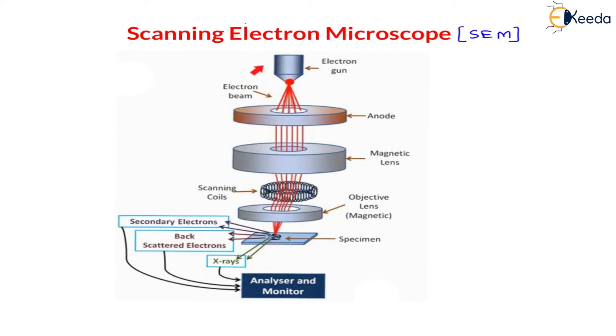Here you can see the actual diagram and setup of this scanning electron microscope. You will see the electron gun — a gun through which the electron beam comes out. There is also an anode. On this anode we provide a positive charge, and since the electron has a negative charge, the electron beam is attracted towards this anode. The anode has a hole, so the attracted beam passes through this hole and travels to the magnetic lens. The principle of magnetostatic focusing is used here, which I have explained in the previous lecture. This magnetic lens is also called the condenser lens.